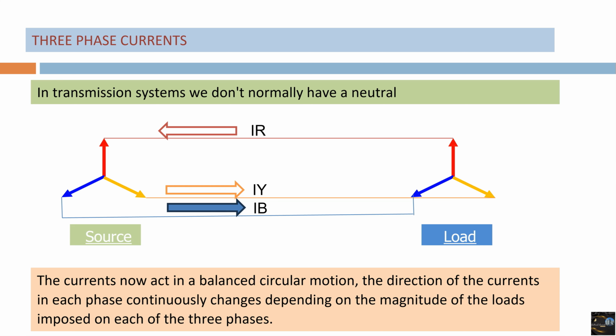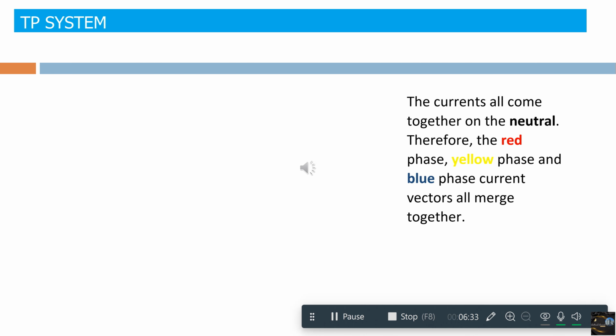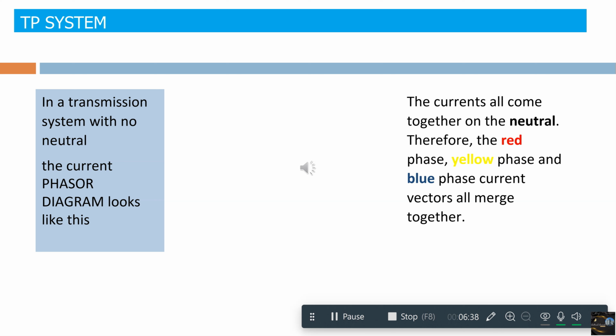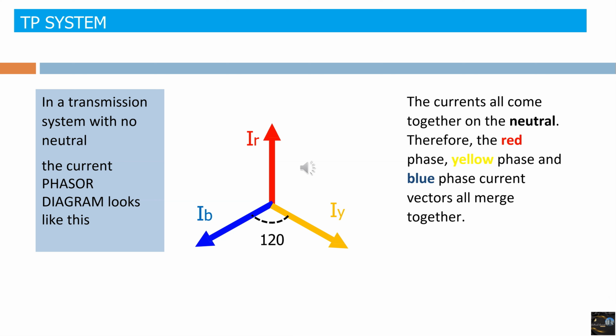But customers require a phase to neutral voltage on the distribution side and a neutral is therefore required. To solve this problem, we have a TPN system. In a transmission system with no neutral, the current phasor diagram looks like this. The currents will come together on the neutral side. Therefore, the red phase, yellow phase, and blue phase currents, all the vectors will merge together.